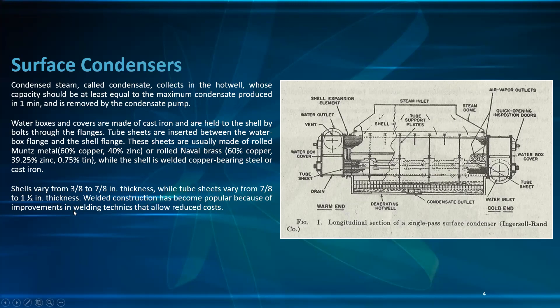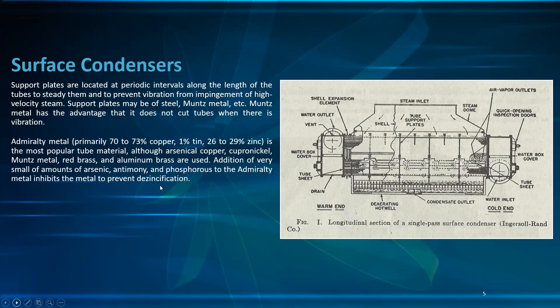Welding construction has become popular because of improvements in welding techniques that allow reduced cost. Support plates are located at periodic intervals along the length of the tubes to steady them and to prevent vibration from impingement of high-velocity steam. Support plates may be of steel, Muntz metal, etc. Muntz metal has the advantage that it does not cut the tube when there is vibration.